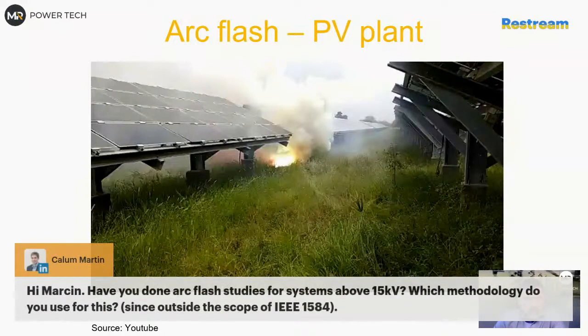Question from Callum. Martin, have you done arc flash studies for systems above 15 kV? Which methodology do you use for it, since it's outside the scope of IEEE 1584? Yes, I did, actually quite a lot. So there are a few tricks I can tell you. If you go above 15 kV, which is a very common voltage in Poland, for example, we sometimes have systems which are 15.75 kV, which are slightly above the IEEE equation. And it was tested that we can extend, and results are still okay up to 36 kV.